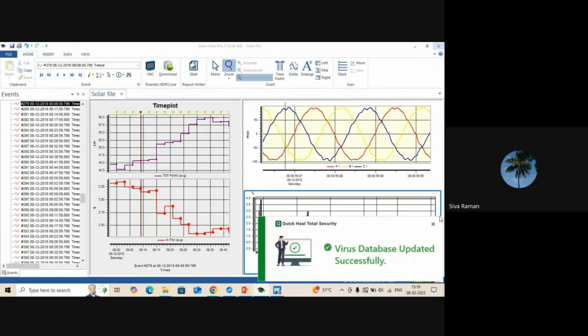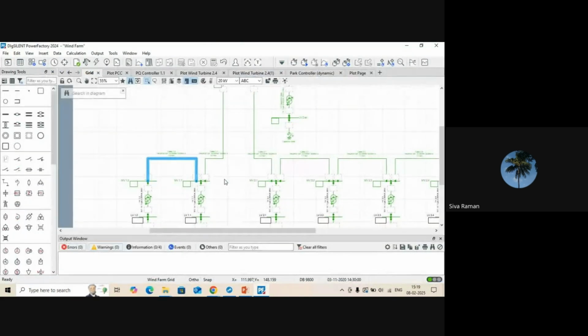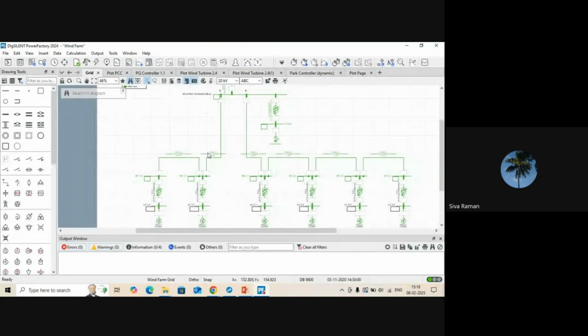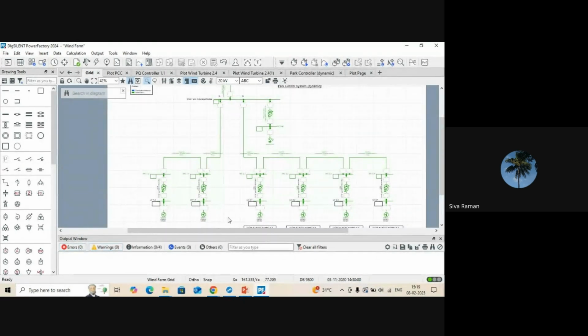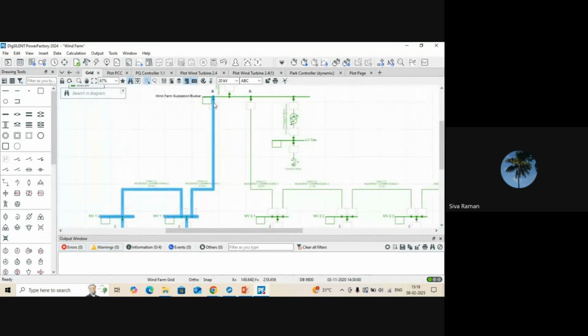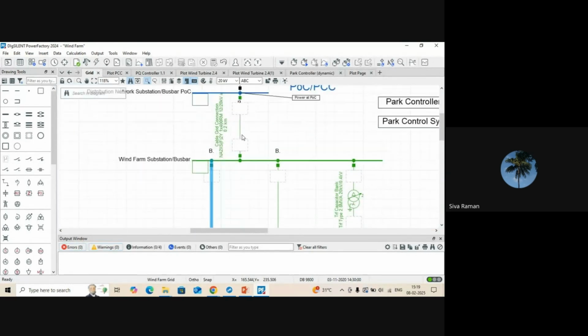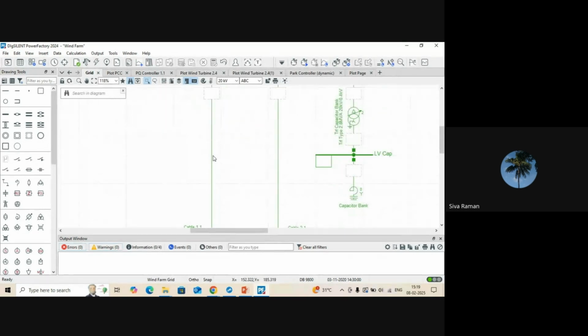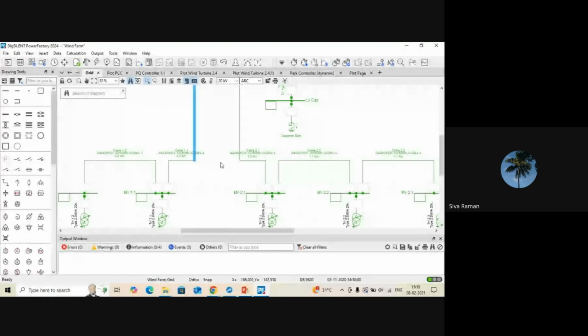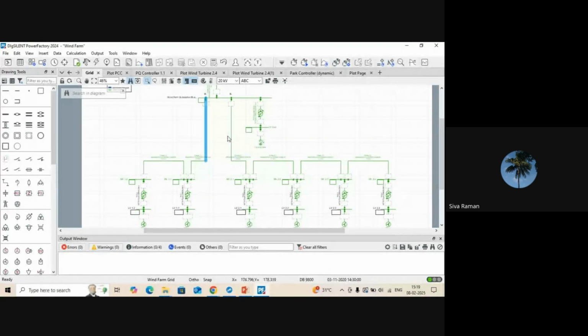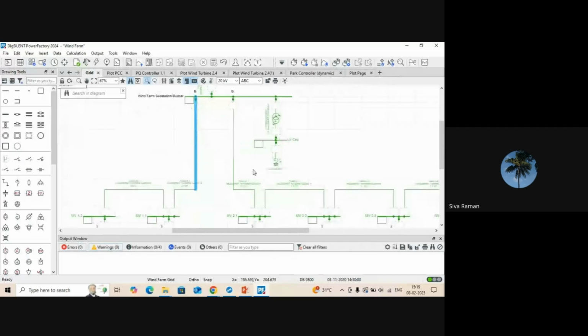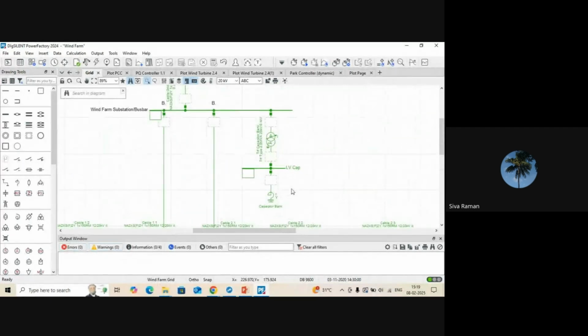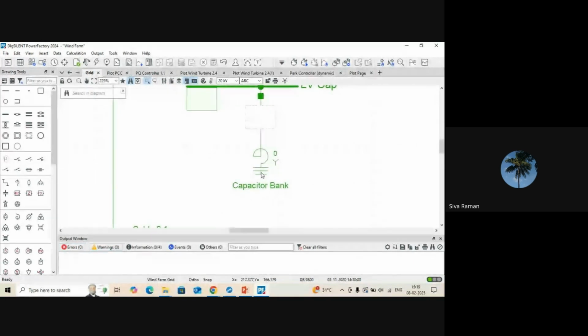Just a minute, I will close this one. So it has two collector network feeders. Two wind turbine generators are connected to the main bus bar at 20 kV through one line. The other 4 turbines are connected to the bus as a second line, and we also have one capacitor bank for reactive power compensation.